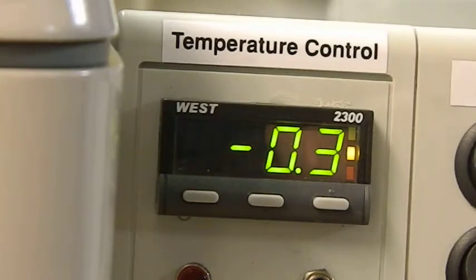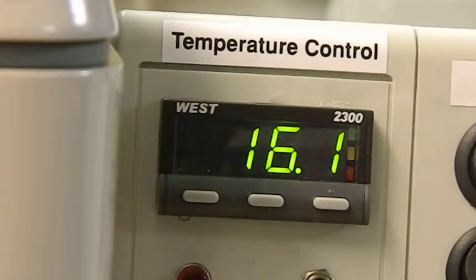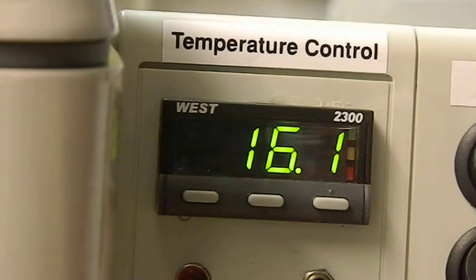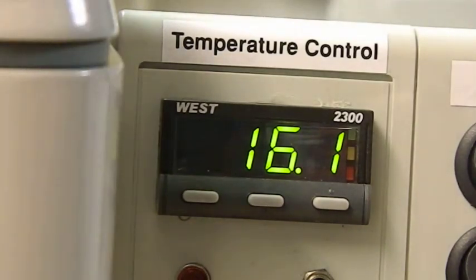Normally 20 seconds, 25 seconds, something like that, without pressing any buttons until it'll time out. When it comes up again, because we've put that in, you've adjusted the reading on the display down by 0.3 of a degree. So it should come up and read 16.1. The set point being 16.1, it should come up and read 16.1. So we'll just wait for this there. There we have it. Okay, 16.4 to 16.1, and it's now holding steady at 16.1. So the calibration is actually finished now. If I check the thermometer inside, it's exactly 16.1, and the controller is also saying 16.1.